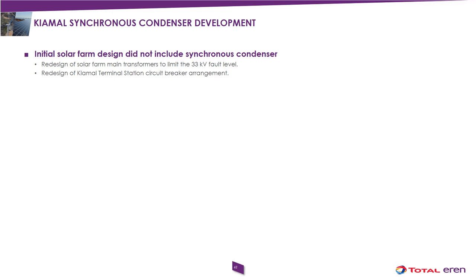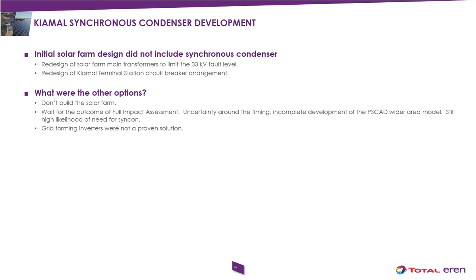So now I'd just like to go into a bit more detail about the development of the Syncon. It almost goes without saying that the initial solar farm design did not include the synchronous condenser. Its inclusion necessitated a redesign of the solar farm main transformers to limit the 33 kV fault level, and a redesign of the Kiamal terminal station circuit breaker arrangement. But what were the other options? There was one, don't build a solar farm. Grid forming inverters were not a proven solution. And finally, wait for the outcome of the full impact assessment.